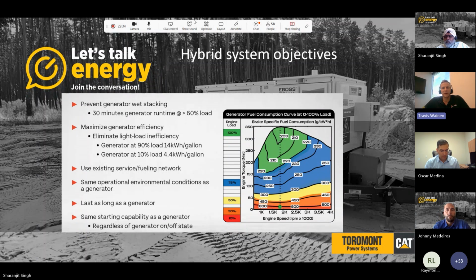To prevent wet stacking, you have to go out and load bank the generator to keep that emission system cleared out. So with the hybrid system, one of the first objectives is to prevent that engine from wet stacking, because that can cause significant damage to the engine if the emission system plugs up. With the hybrid objective, when we turn that diesel engine on, we want it running for about 30 minutes at least 60% load to make sure it gets good and hot, the catalyst heats up on the exhaust, and the emission system stays nice and clean.